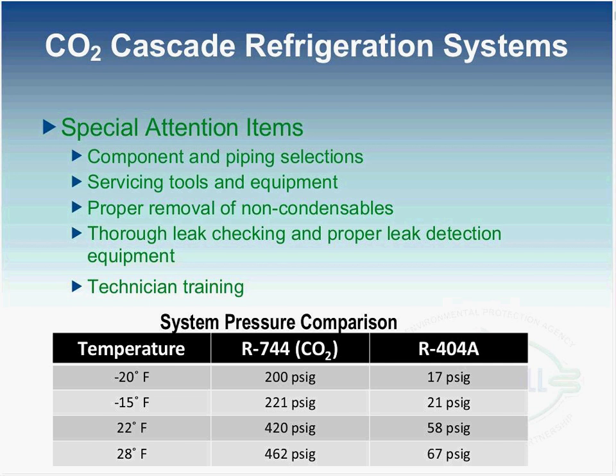It's going to be very important that the installation has all non-condensables very thoroughly removed. Very important for both the performance and the operation of the system. There are a few things you can do to make sure there are no non-condensables in the system. First, use high-grade CO2. A very pure CO2 is a pretty substantial assistance there. You'll also need to filter the refrigerant as it's being added to the system, and then make sure a proper evacuation is conducted prior to charging the system.